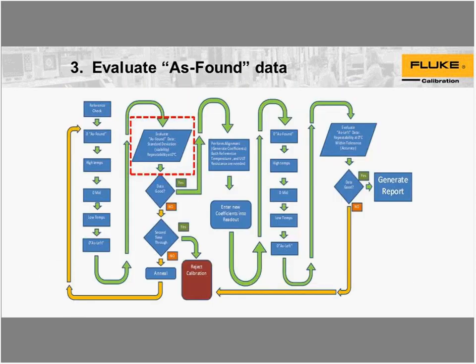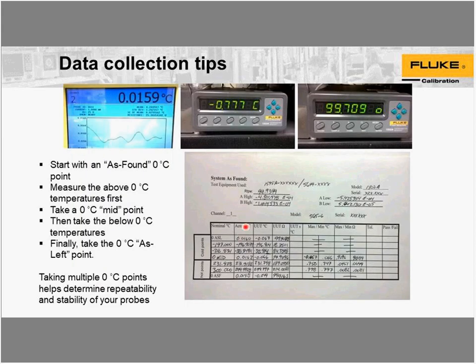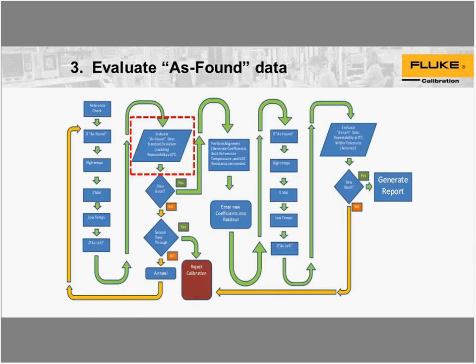Right, so moving back, where are we going? After we've collected all the as found data, and that includes reference temperature, let me go to the slide again. It includes the actual reference temperature recorded by our 1595A and our reference SPRT. It covers the temperature that our DUT is reading and the resistance that your probe is reading through your readout. Okay. So record the max of both the temperature and the resistance in this case. Right. When we evaluate the data, what we're looking at is the error between the reference and the UUT.